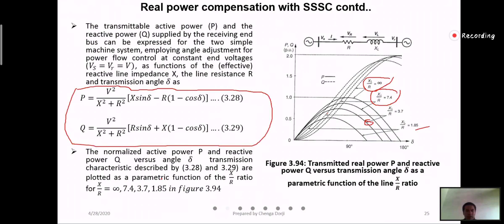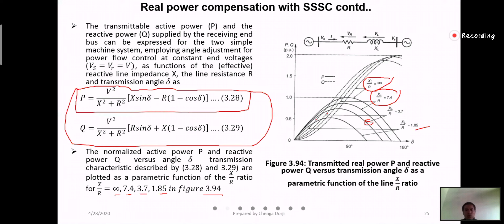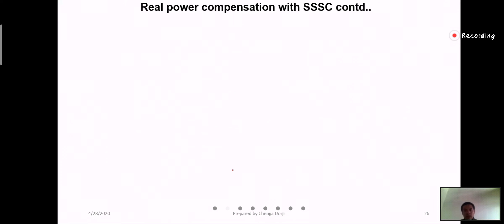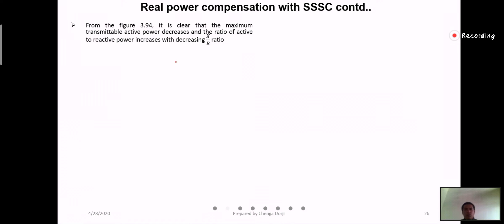The normalized active power P and reactive power Q versus angle (delta) transmission characteristics — equations 3.28 and 3.29 — are plotted as parametric functions of X/R ratio for values of infinity, 7.4, 3.7, and 1.85. From figure 3.94, it is clear that the maximum transmittable active power decreases, and the ratio of active to reactive power increases with decreasing X/R ratio.